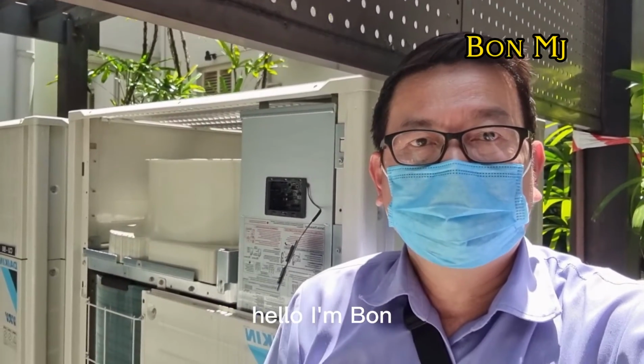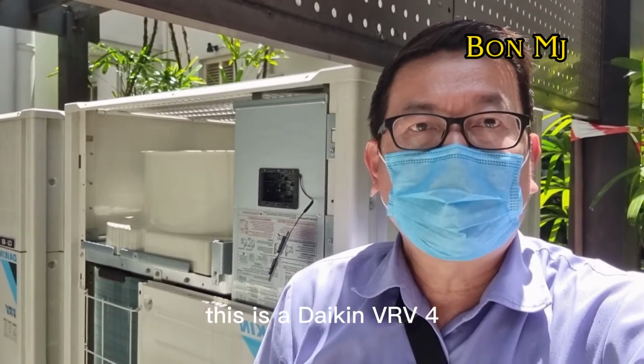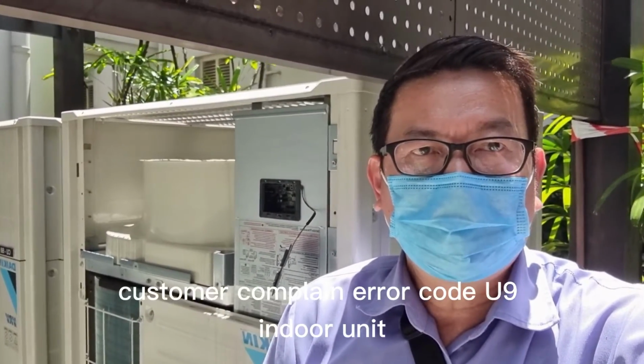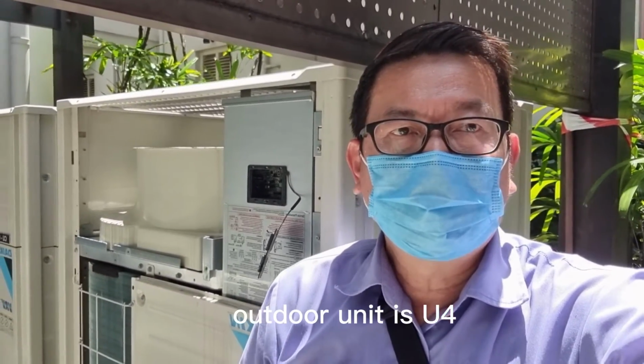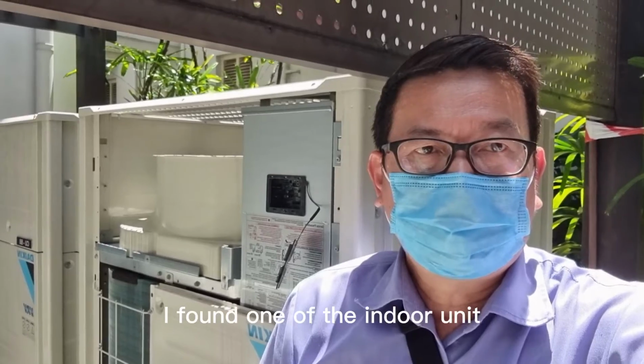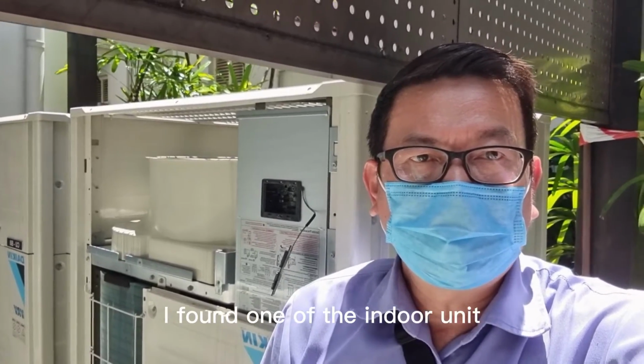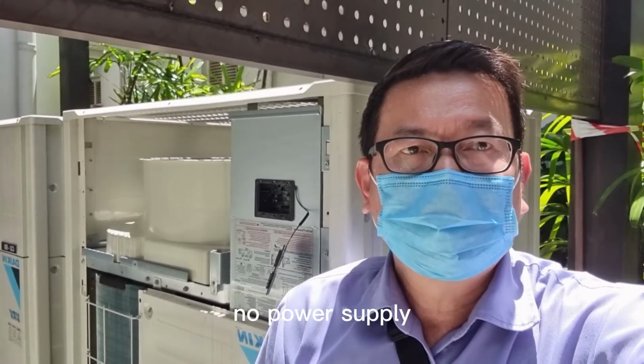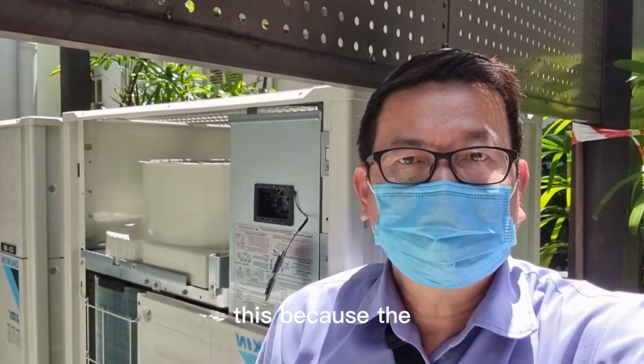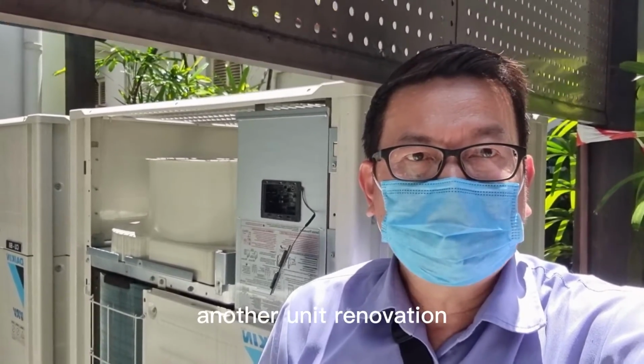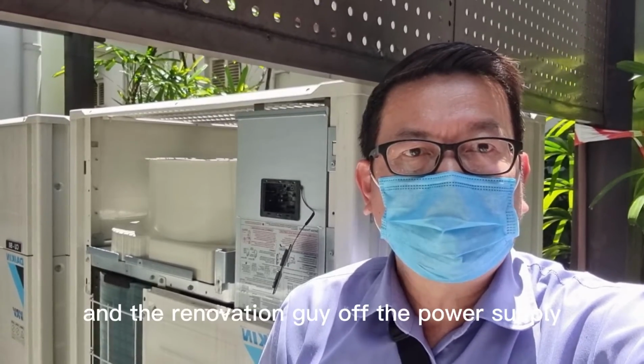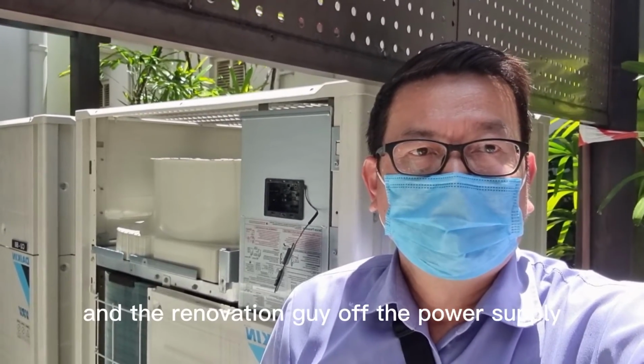Hello, I'm Bon. This is a Daikin VRV4. Customer complained the error code U9 on the indoor unit, but the outdoor unit shows U4. I found one of the indoor units has no power supply. This is because another unit's renovation work had the power supply switched off by the renovation guy.